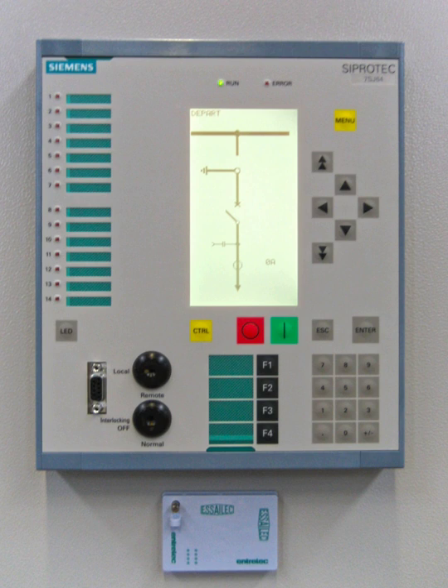Topic: distance impedance relay. Distance protection detects both voltage and current. A fault on a circuit will generally create a sag in the voltage level. If the ratio of voltage to current measured at the relay terminals, which equates to an impedance, lands within a predetermined level, the circuit breaker will operate. This is useful for reasonably long lines, lines longer than 10 miles, because their operating characteristics are based on the line characteristics.